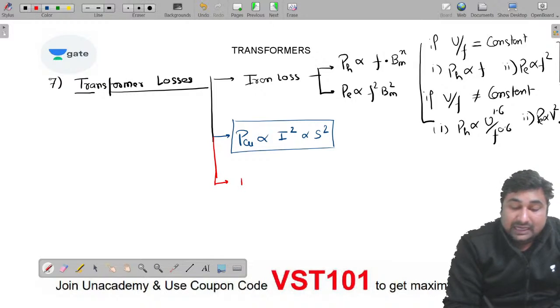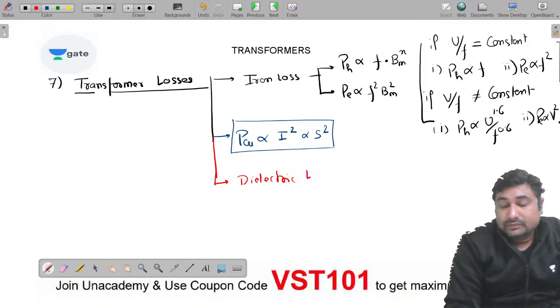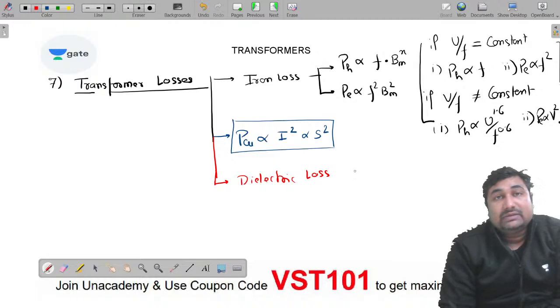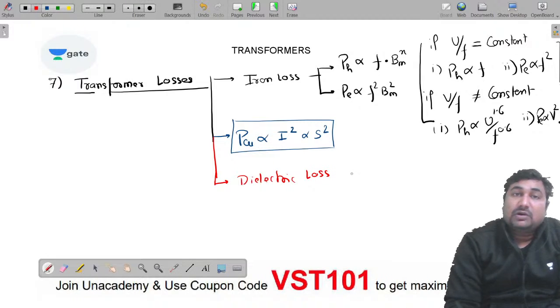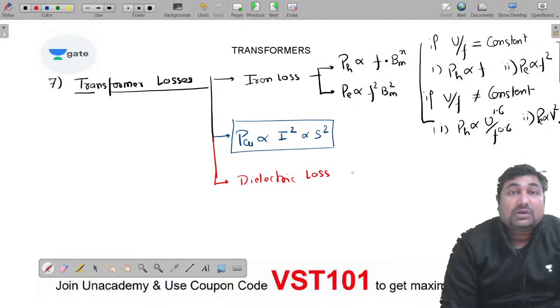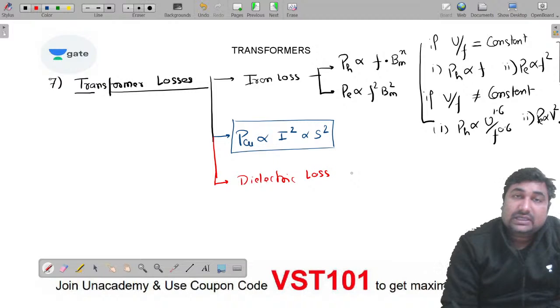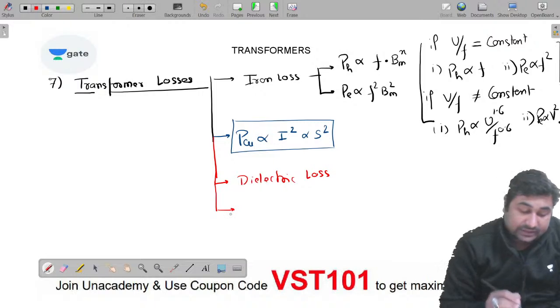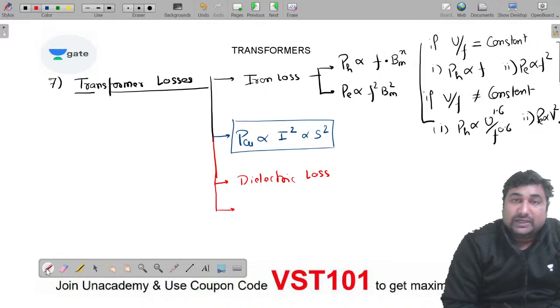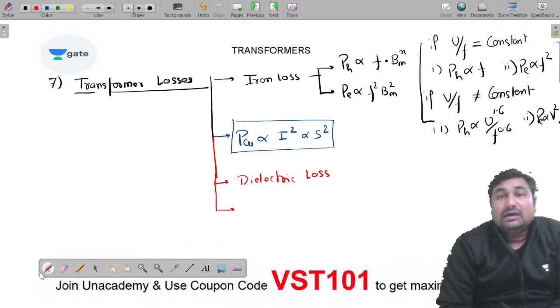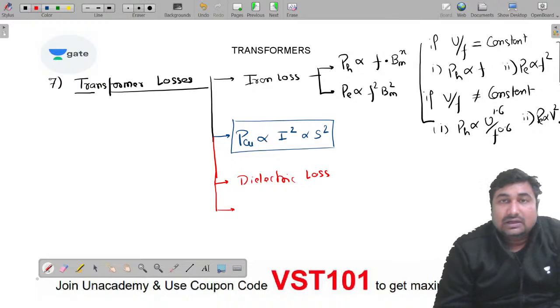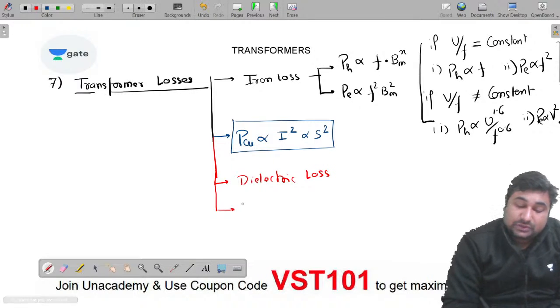Next is your dielectric loss and stray load loss. So dielectric loss is a constant loss, occurs in the transformer oil and insulating materials of HV winding. Transformer oil serves two purposes. कौन कौन से? It provides cooling to the transformer as well as it provides isolation, electrical isolation. Okay, so you can also say it provides a dielectric strength to the gap between the body and the conductor. Okay, next is your stray load loss.